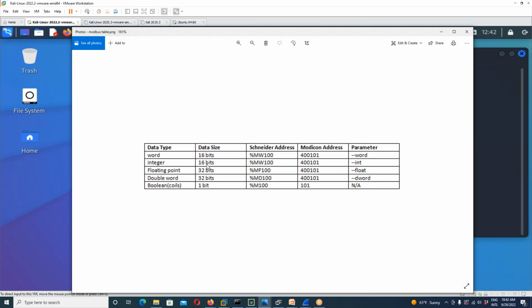There's 16 bits. If we're going to do a floating point, it's going to be MF. If it's a double word, it's going to be MD. If it's Boolean - the coils, remember coils are simply on or off - it's percent M100, or just 101 in Modicon. This particular tool should work with both types of addresses, both the Schneider address and the Modicon address. The Modicon address is part of the open source specification of Modicon, and Schneider uses that too, but they try to use a proprietary address.